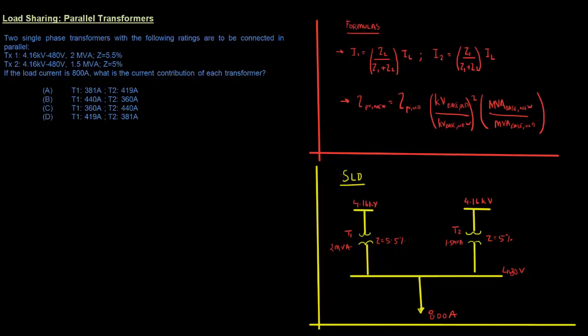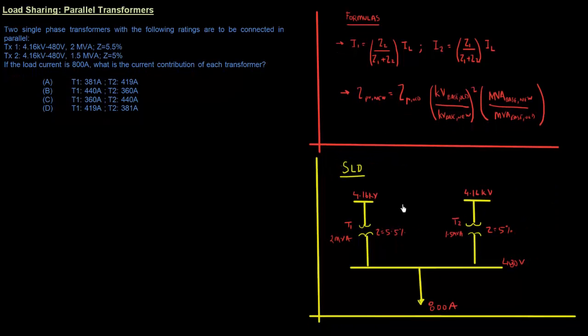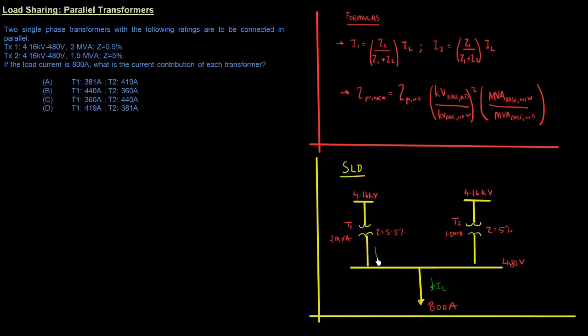Looking at the single-line diagram: we have transformers T1 and T2, both with primary voltage 4.16 kV connected to a 480 V bus. T1 is 2 MVA with 5.5% impedance, T2 is 1.5 MVA with 5% impedance. The load current IL is given as 800 amps. What we need to find is I1 and I2.